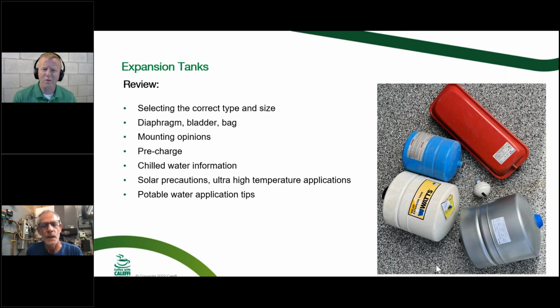Anything else that you can think of, Bob? Any other downsides there? I did look at that today. I looked at the two different tanks, and one says it's got an EPDM diaphragm and the other one says butyl EPDM. So I don't know if the bladders are changed from one to the other. Again, that would be a manufacturer specific question. I would think it's the same material used in both of them, but if you did use it on a hydronic system, you would want to make sure the bladder can handle not only water, but glycol or any chemicals that you might put in there.